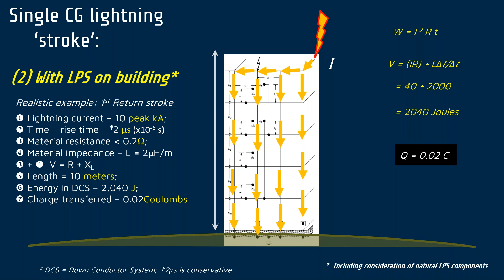We talk about the voltage, you know, we have enormous voltages. If you back up the pipe at the bottom of your system, trying to get this lightning current into the ground, if you back it up, you are going to get over voltages. So the next part of the lightning protection system is dealing with dangerous sparking from the lightning protection system.